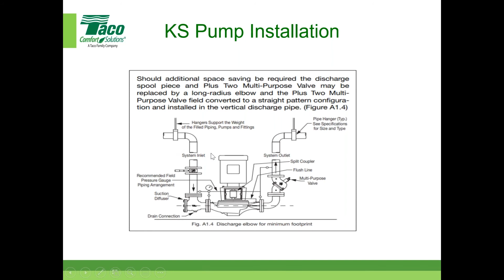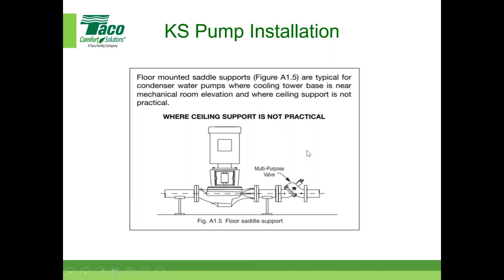Where ceiling support is not practical, you can support it with saddle supports going straight down. You need some straight run of pipe, so it takes up a little more room, but we do see that near a cooling tower base or near room elevation, ceiling support is sometimes not practical. If you look through our instruction manuals, you can get more ideas on stuff like that.